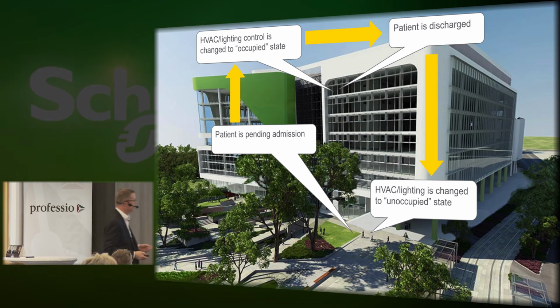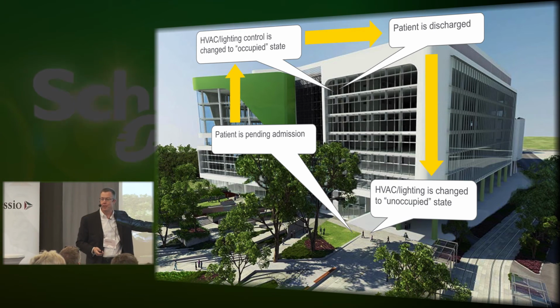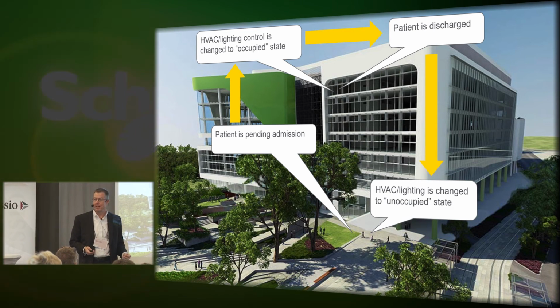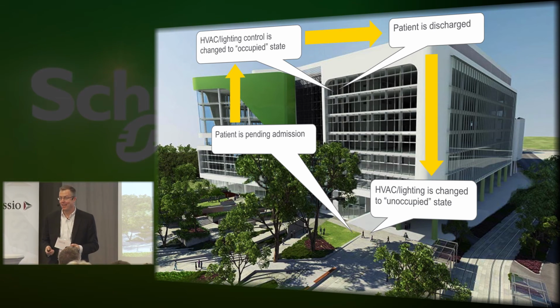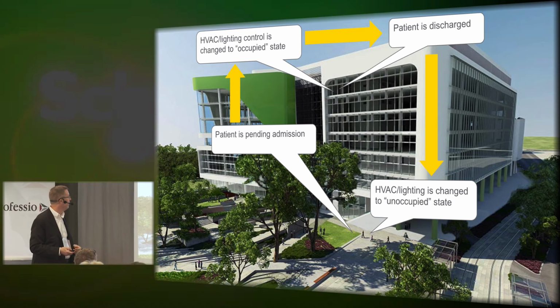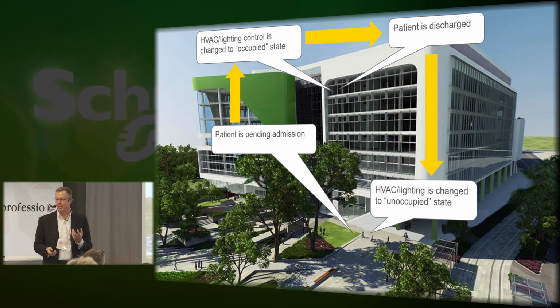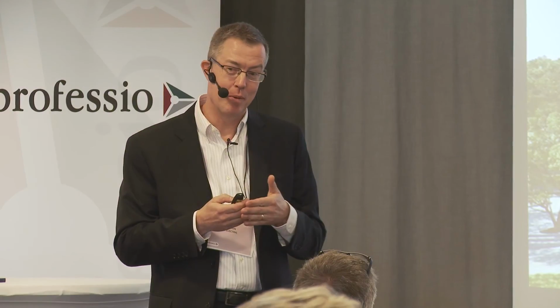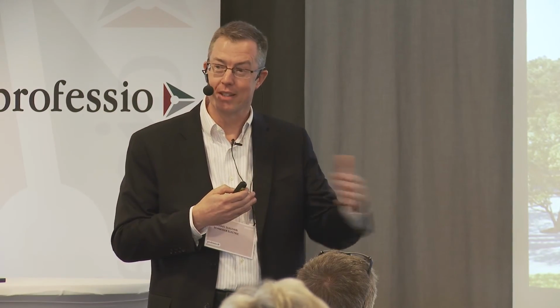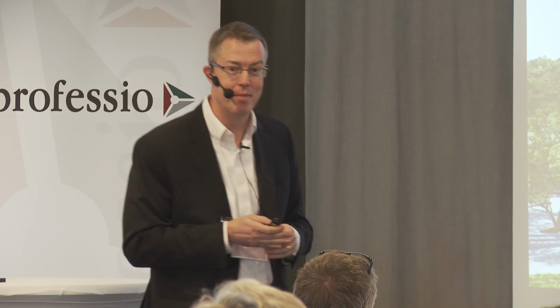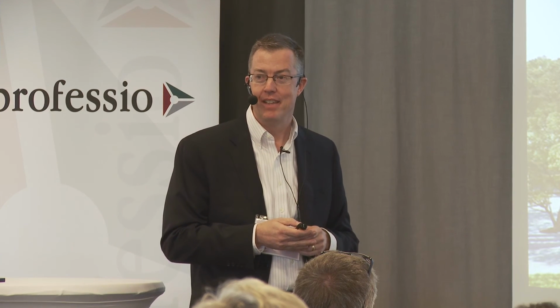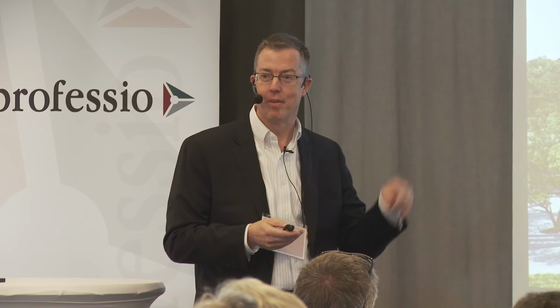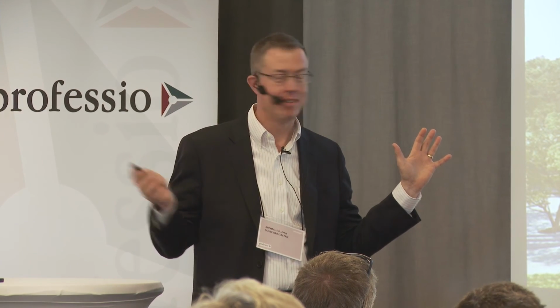So when a patient is coming in, say through the emergency room and pending admission into room 305, only then do we turn on the HVAC and lights. We know that patient will arrive in that room within 5 to 20 minutes, depending on how long it takes to get up there, and by that time the HVAC and lighting is fully operational. You would have thought it was on all day, but it wasn't.